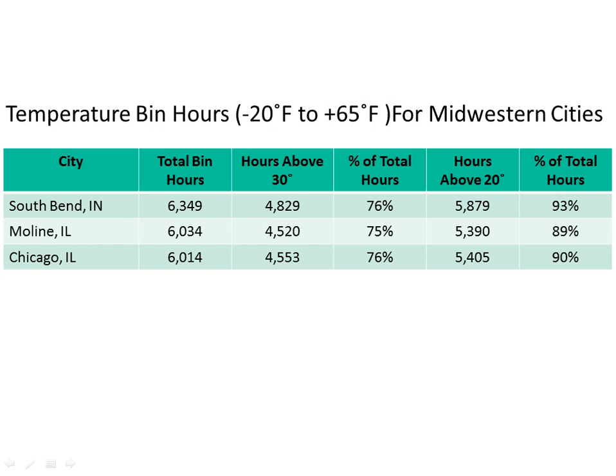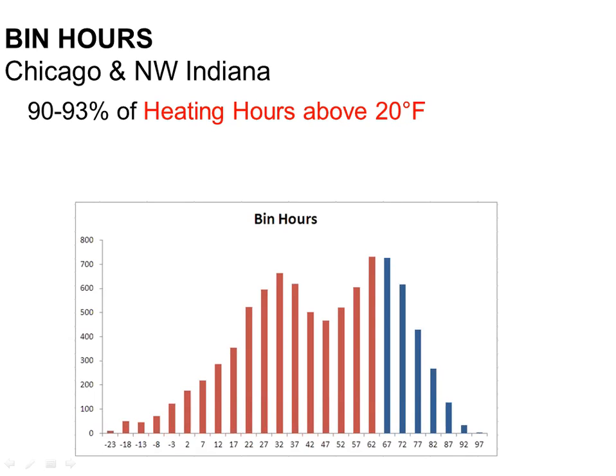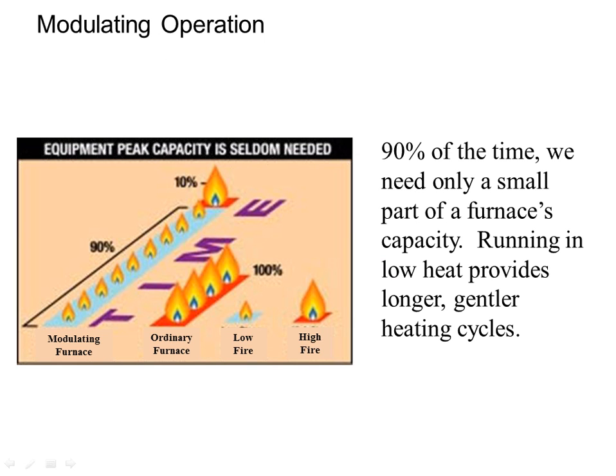So we were talking about how many hours are in each bucket, right? So we got a lot of heating hours between 20 and 65 degrees outside. This kind of shows you visually how much heating we have compared to cooling. This slide was kind of an example of what we used to do to explain 2-stage equipment to people, but it does apply to the modulating concept even more so.